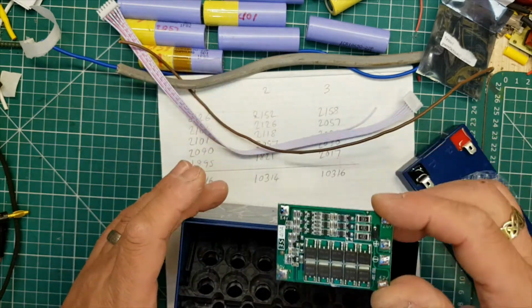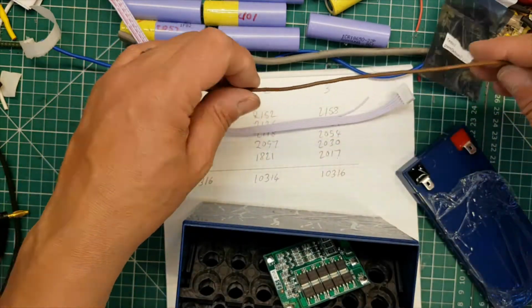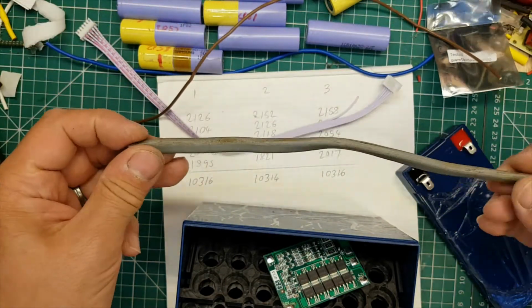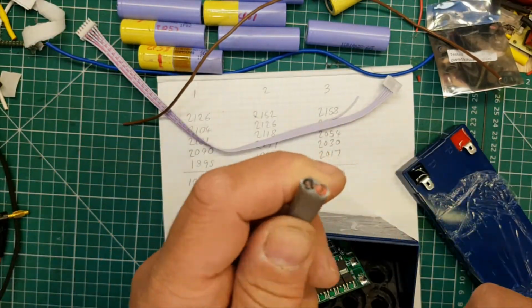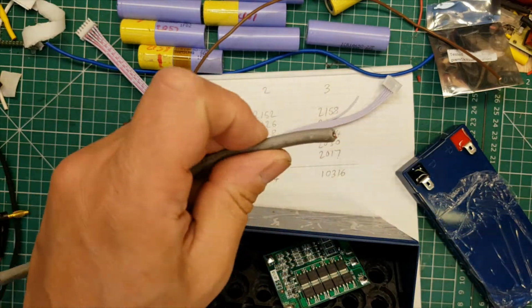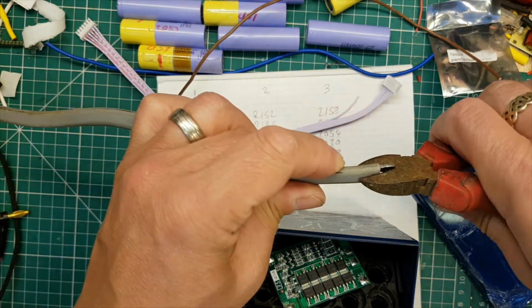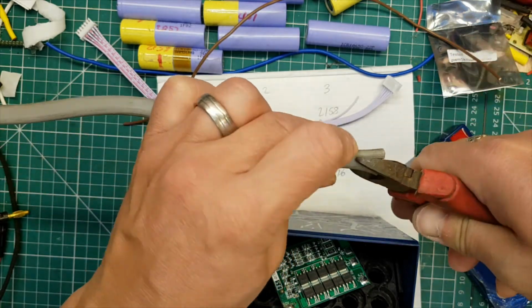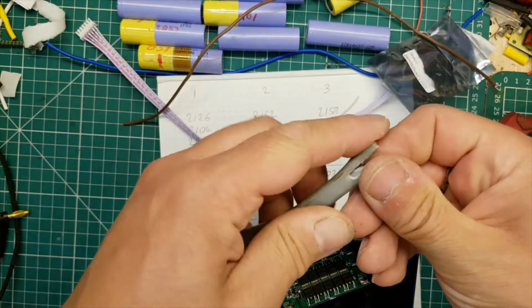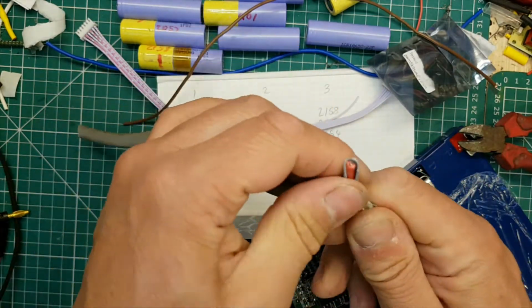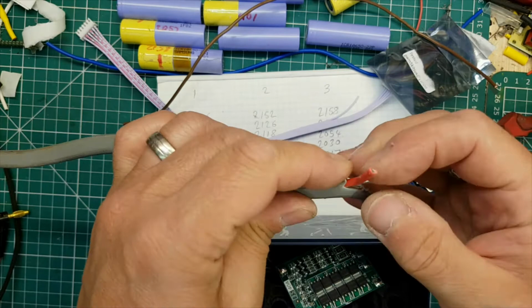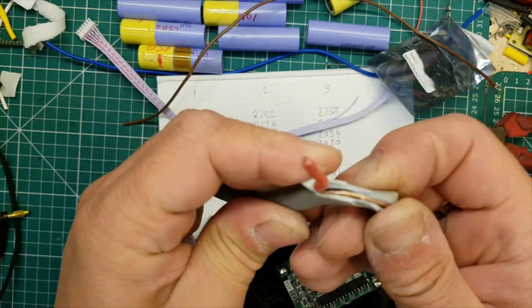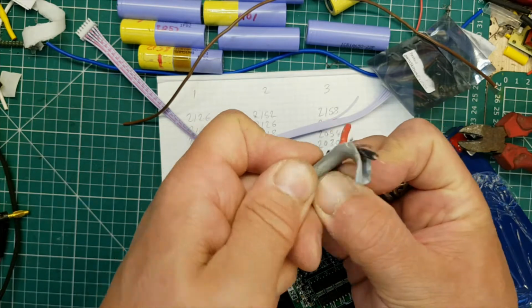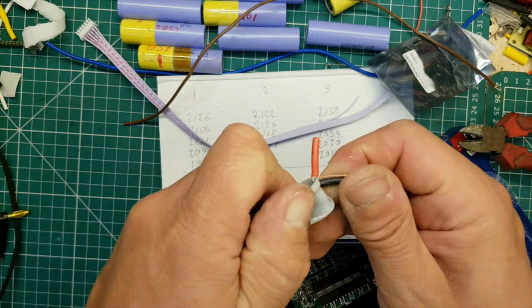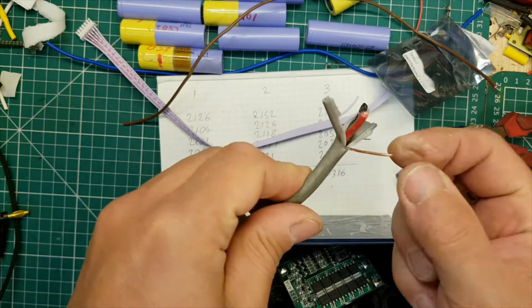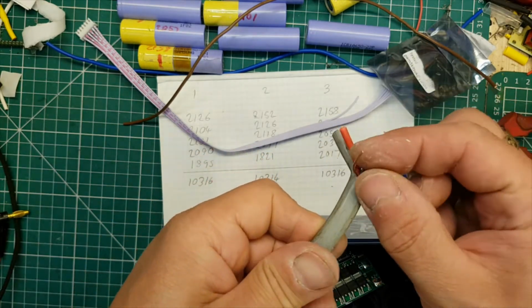So that is going to go in with this. To link it all together, I'm going to use good old UK Twin and Earth, a 2.5mm T&E, the same as used on power ring main circuits. Inside, if you open it up, you find a red conductor with a cross-sectional area of 2.5mm, a black conductor also 2.5mm, both solid copper, and then the earth is 1.5mm and unsheathed.